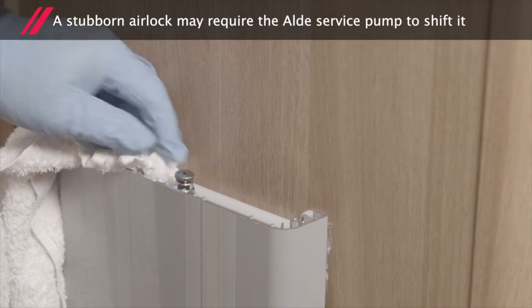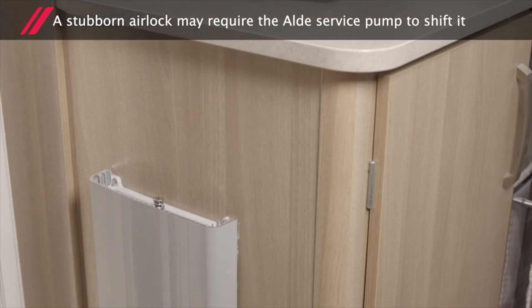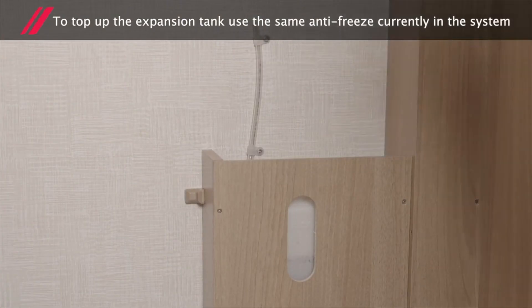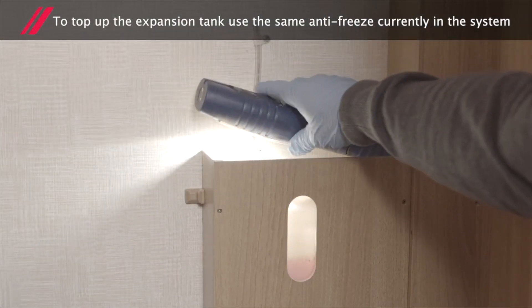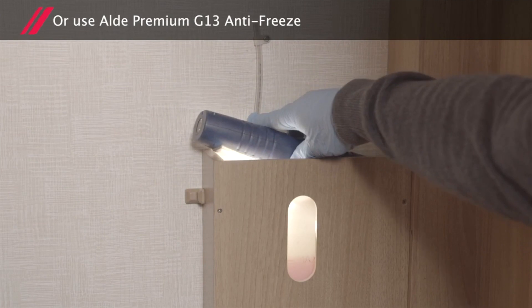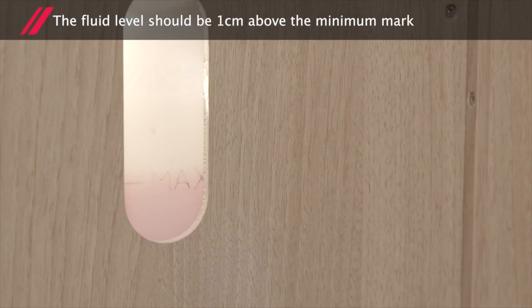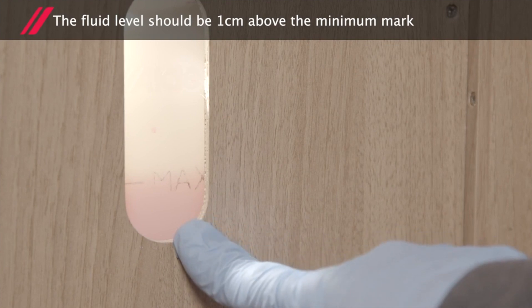A stubborn airlock may require the Alde service pump to shift it. To top up the expansion tank, use the same antifreeze currently in the system, or you can use the Alder Premium G13 antifreeze. The fluid level should be 1cm above the minimum mark.